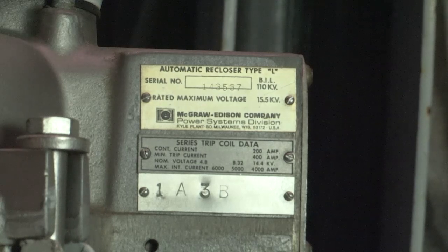Now this first fast curve is basically for when a storm is happening and there are trees blowing, and a tree branch falls on the line. The recloser will see this, trip instantaneously, trip off and on once. That's when you get those lights in your house blinking off and then back on again. And if they do come back on, then the fault is gone, the tree branch is gone, and everything's fine.